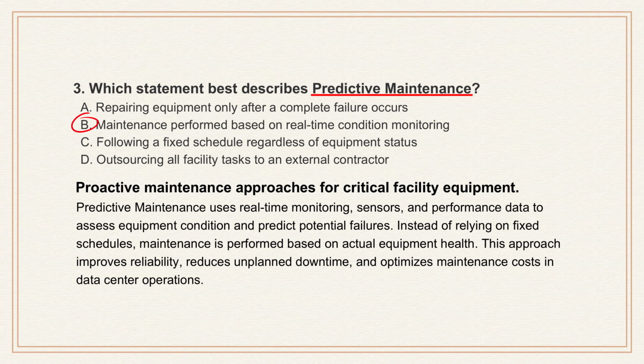We're really talking about applying data science to the building itself. This means you have sensors on all your critical equipment, chillers, generators, UPS systems. These sensors analyze vibration signatures, oil quality, heat patterns, load trends, looking for signs of trouble.